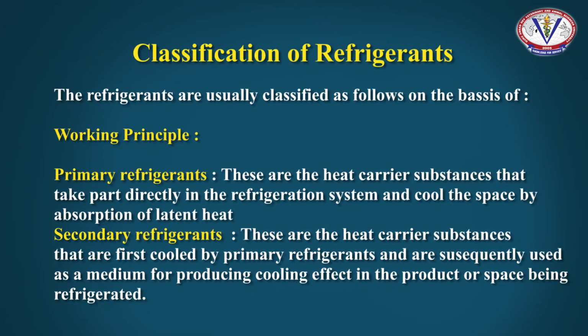Now we'll go for classification of refrigerants. The refrigerants are usually classified on the basis of working principle. They are primary refrigerants, and these are the heat carrier substances that take part directly in the refrigeration system and cool the space by absorption of latent heat. And second is secondary refrigerants. These are the heat carrier substances that are first cooled by primary refrigerants and are subsequently used as a medium for producing cooling effect in the product or the space being refrigerated.